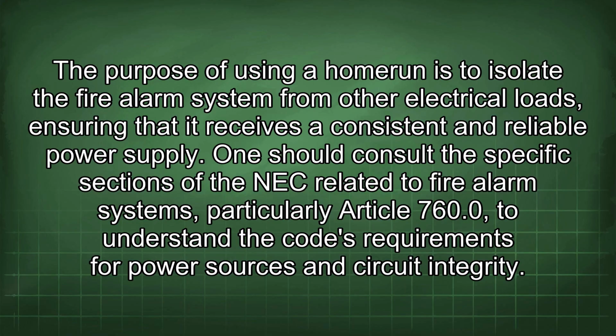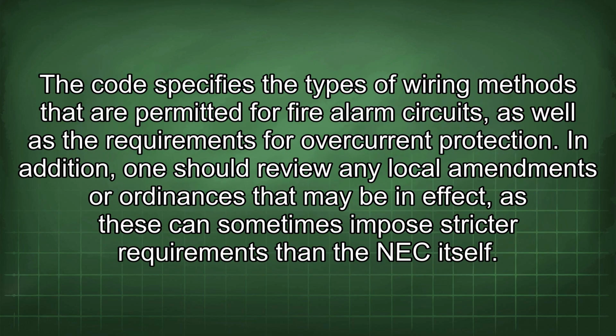One should consult the specific sections of the NEC related to fire alarm systems, particularly Article 760, to understand the code's requirements for power sources and circuit integrity. The code specifies the types of wiring methods that are permitted for fire alarm circuits, as well as the requirements for overcurrent protection. In addition, one should review any local amendments or ordinances that may be in effect, as these can sometimes impose stricter requirements than the NEC itself.